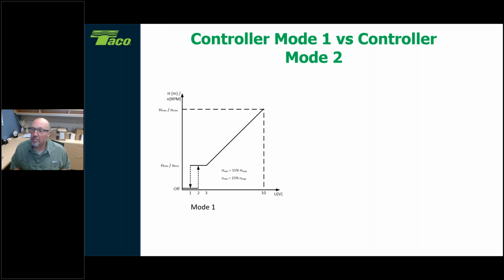So now on the mode dial, that mode dial again that I was showing you before, mode number 1 shows our 0 to 10 signal here. Again, this is all dependent upon the equipment that's sending the signal into us, so we're going to have to verify that data from that manufacturer. For example, here's mode 1, which means once you get down to 3 volts, it's going to give you a steady speed of the circulator until it gets down to less than 1 volt, and then the circulator shuts off. Then it waits until the voltage is above 2 volts. Then it has a minimum speed that you would set it for. It operates at that until it gets to 3 volts, and then we operate on that line.